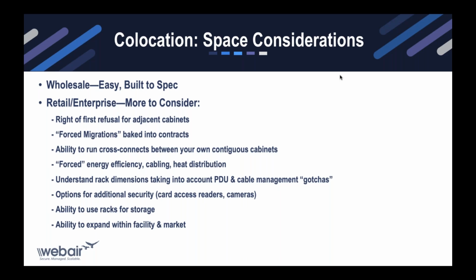If I'm going into a cabinet with deeper depth, where I can use zero U PDUs and cable management instead of doing those horizontally, I'm saving space. A vendor who can provide more power density means I'm getting a lot more for my money. I might not need it day one, but as equipment gets denser in the future, there's tons more efficiency. I might get 1.5 to 2 times the amount of compute and storage out of a cabinet for the same price.